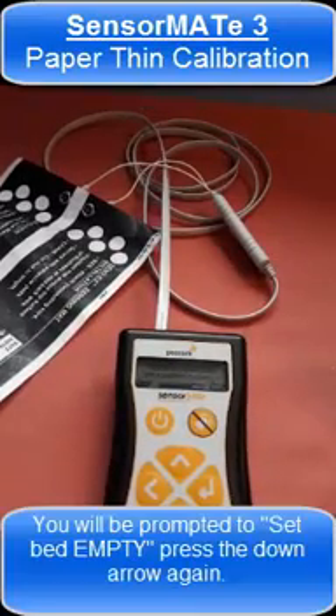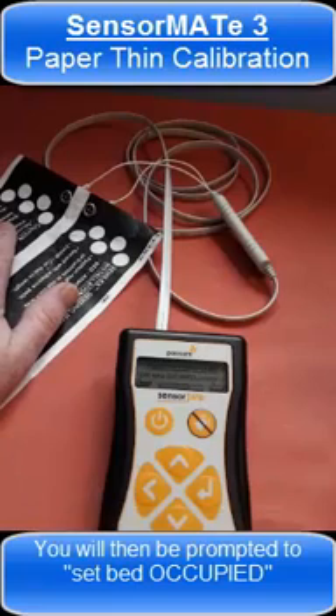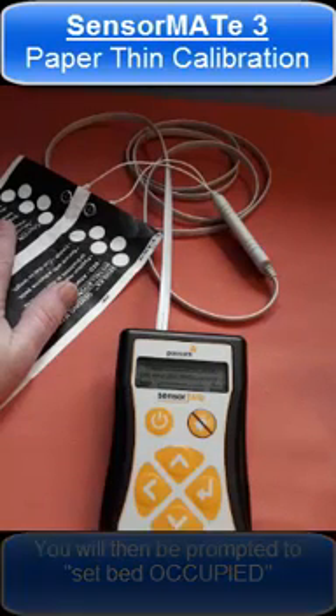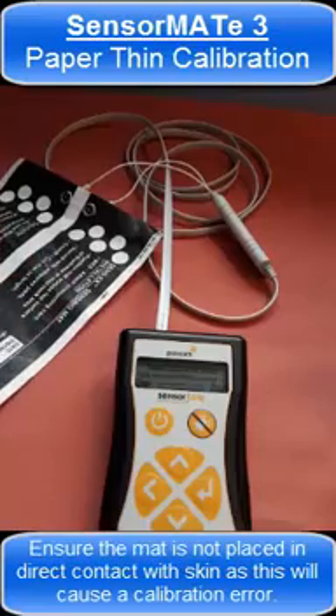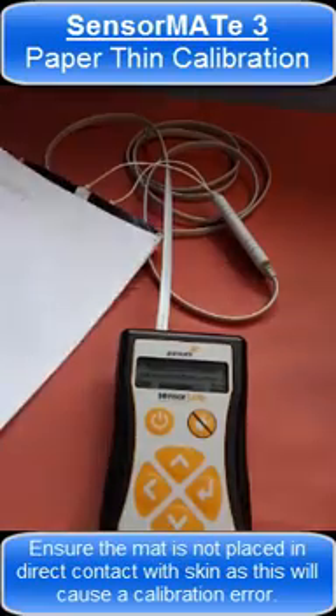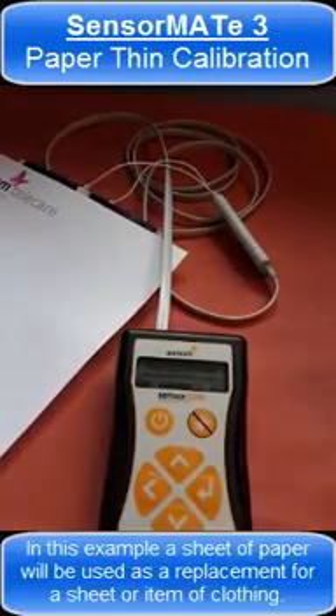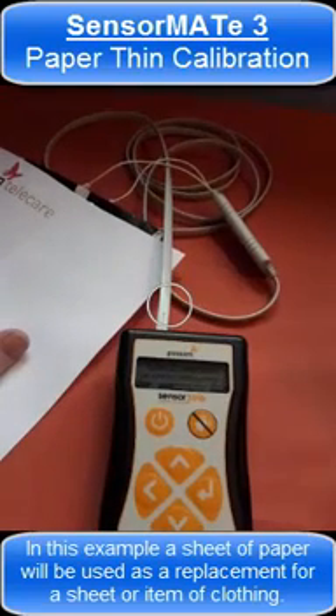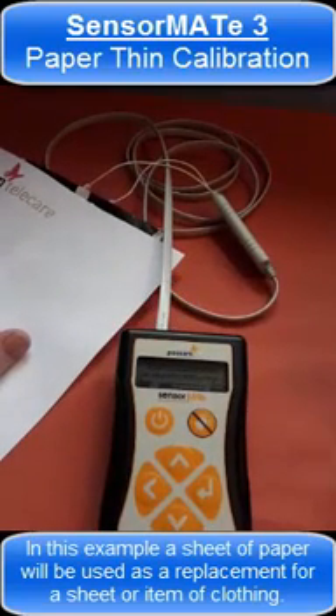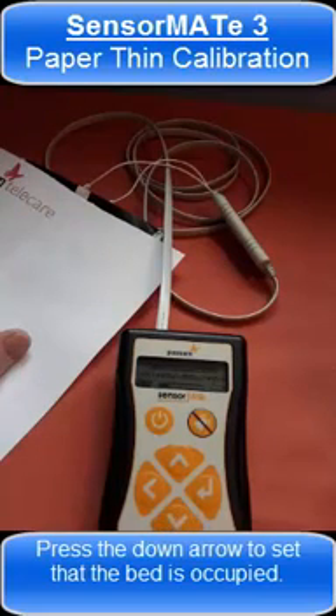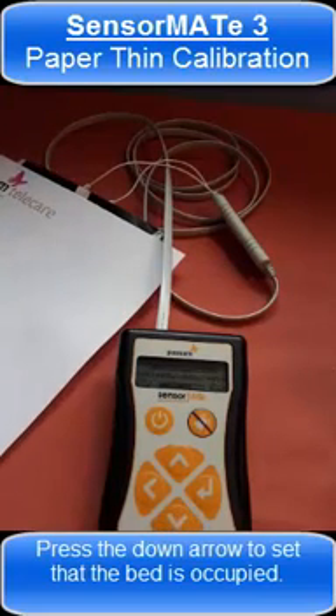You will be prompted to set the bed empty. Press the down arrow again. You will then be prompted to set the bed occupied. Whilst carrying out the calibration process, avoid direct contact with human skin, as this will cause a calibration error. In this calibration example, I'm using a sheet of paper to insulate the human skin from direct contact. Press the down arrow to set that the bed is occupied.